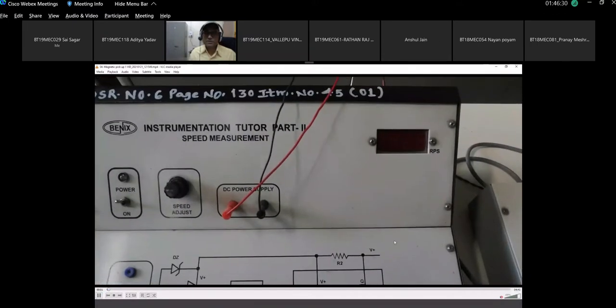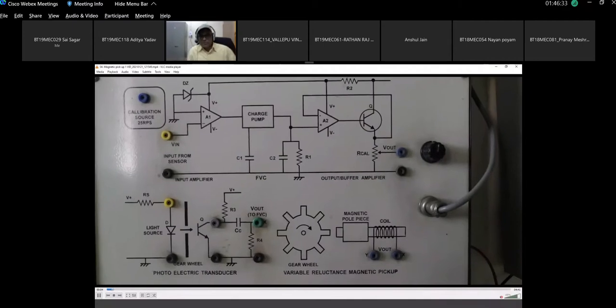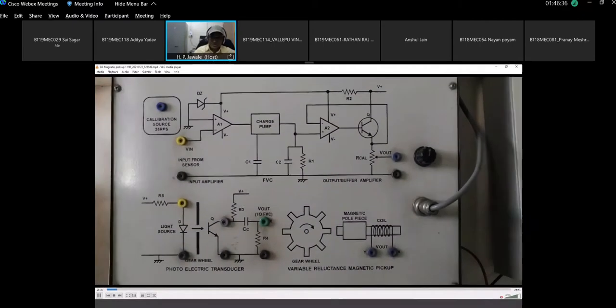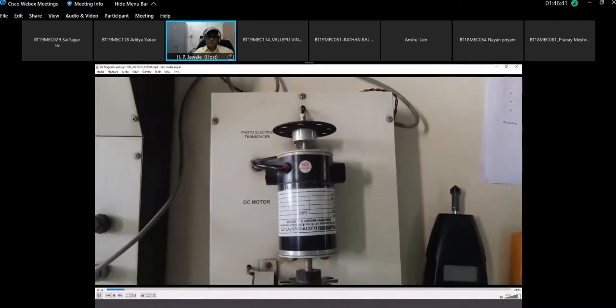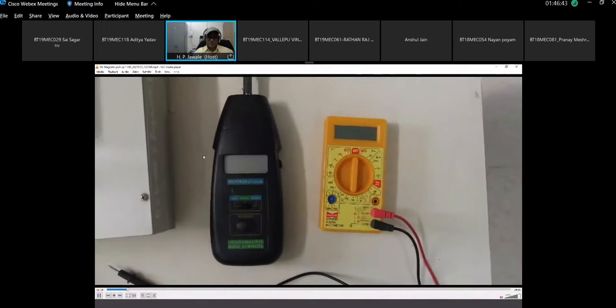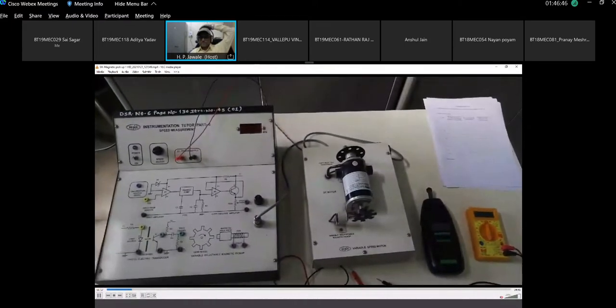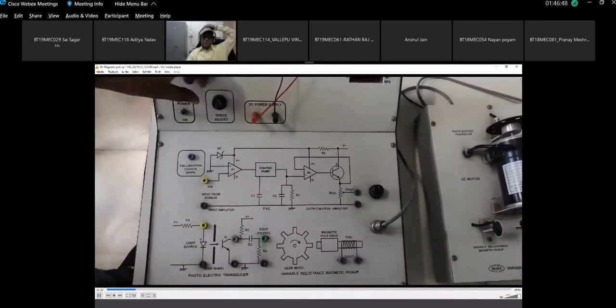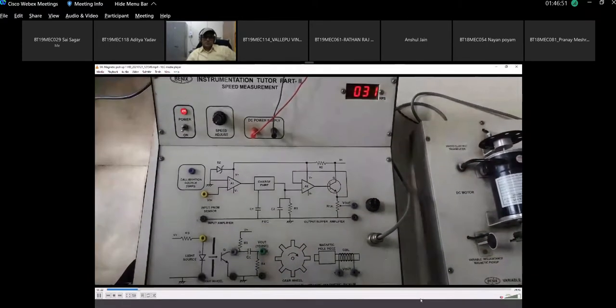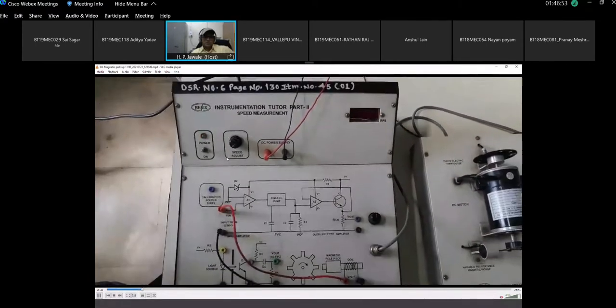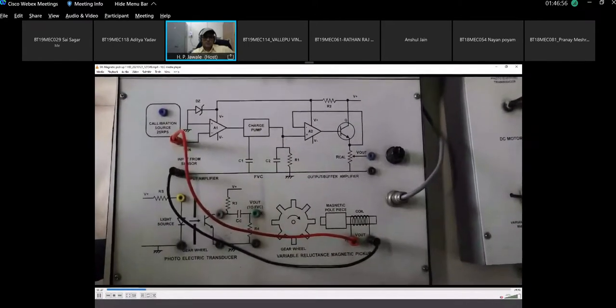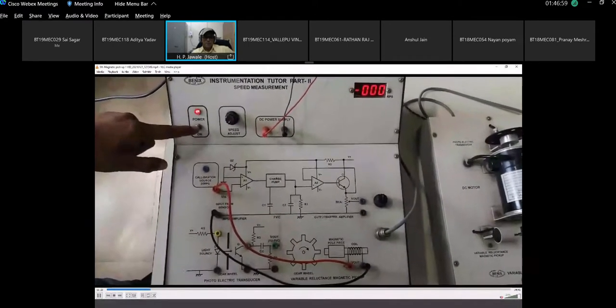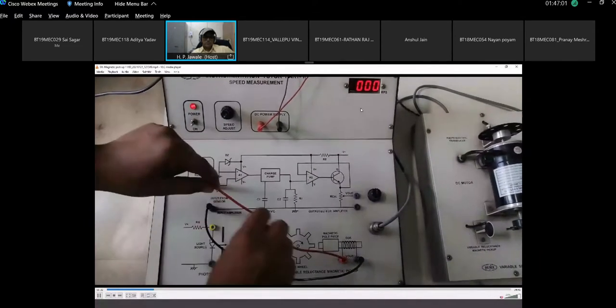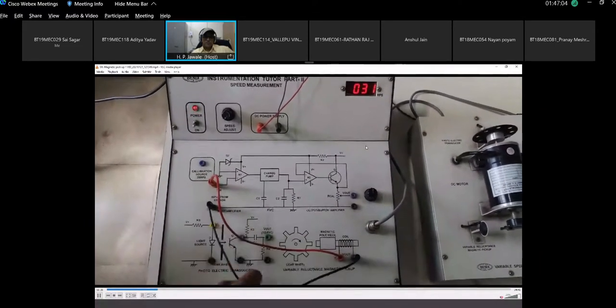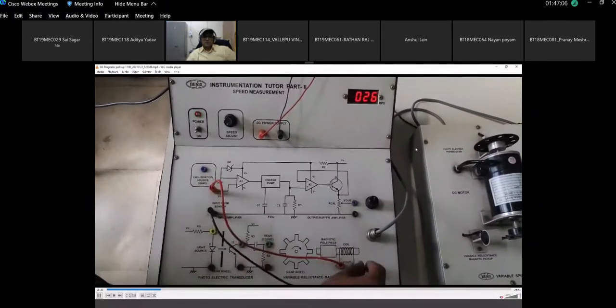You pay attention now to how it is connected. This is the part that will be the gear wheel variable reluctance magnetic pickup. This is a motor unit, and this is the pickup. So speed is 0. You see now, for 0 speed, it should show 0. Condition is done.